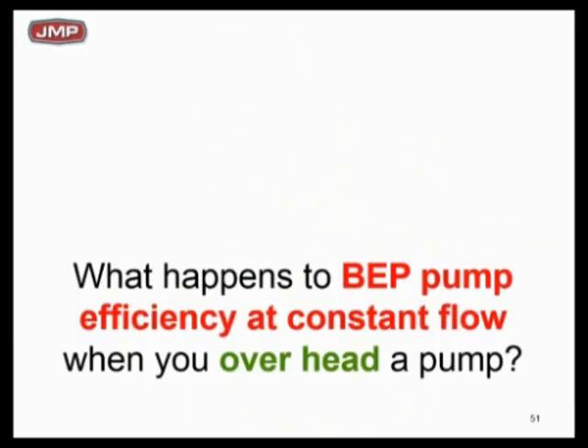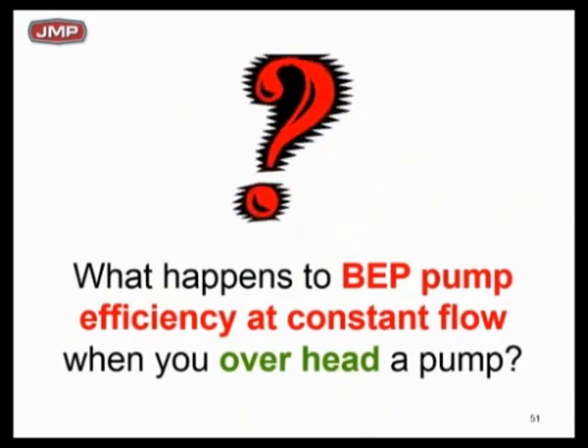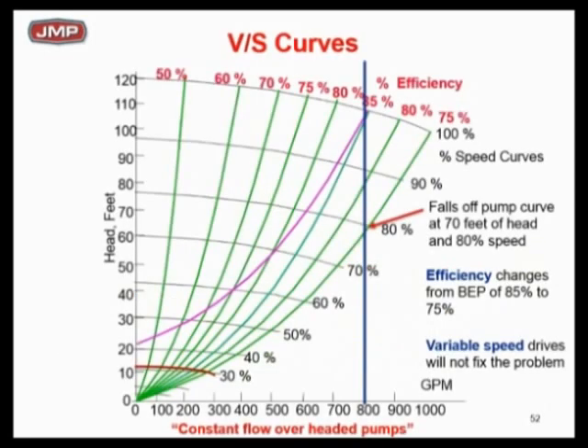What happens to pump efficiency at constant flow when you over-head a pump? We're seeing this issue in lots of places — Chicago, Raleigh, LA, all over the country — because people are buying pumps and just thinking they can put a variable speed drive on it and fix all their problems. You cannot do that, and this is where we're getting into trouble.